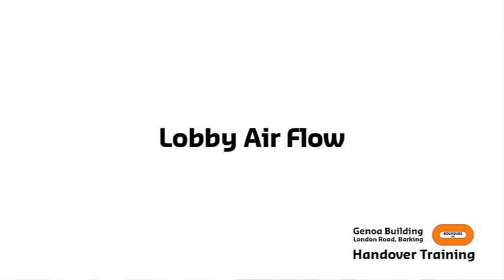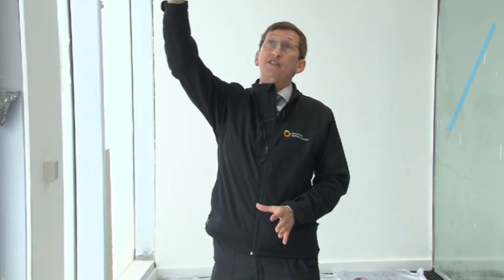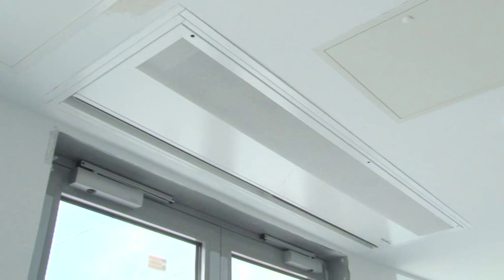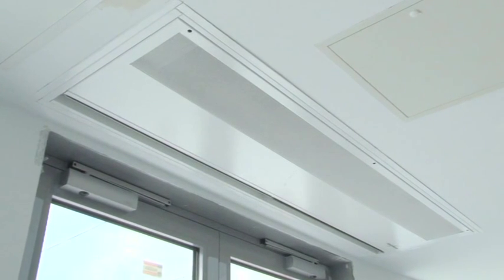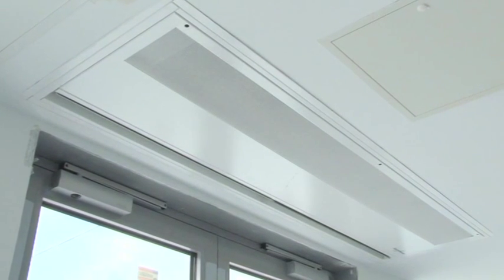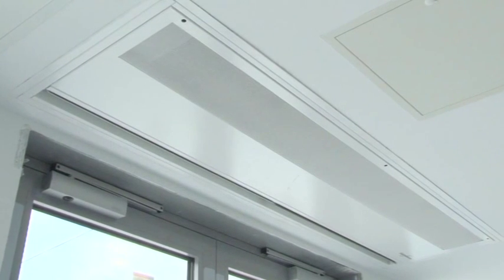Okay, so we're just in the lobby entrance door area for the reception area. And all we're showing here really is there's an air curtain above the door, which will give us a heated airflow over the door as the doors are open, and also to control temperature in this area as well. So there's a control panel on the wall here, which you can adjust the airspeed for the fan running through there, so you can set that to what level's required. So that will be done on commissioning. If it's not right, then it can be adjusted, but it should be set.